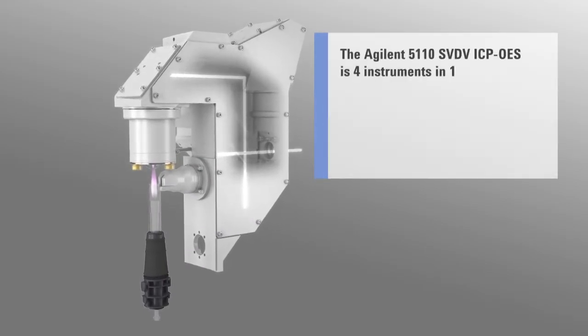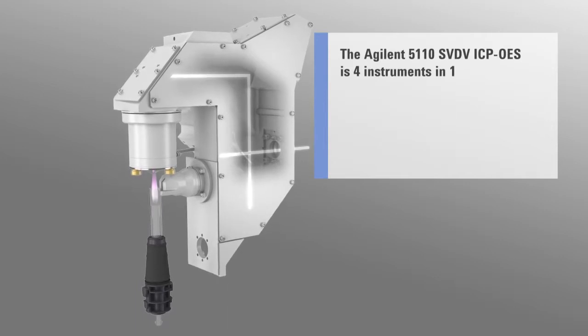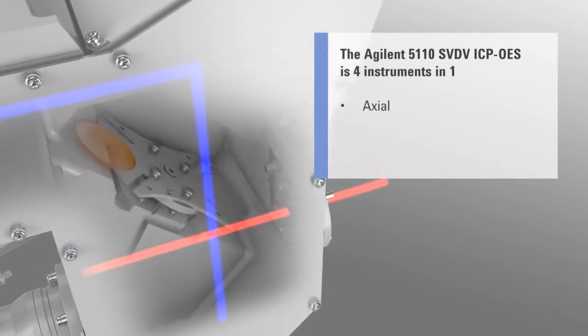In 2014, Agilent released the 5100 Synchronous Vertical Dual View ICP OES with dichroic spectral combiner technology. This set a new benchmark in speed of analysis, cost of ownership, performance and ease of use. The dichroic spectral combiner technology combines the light from the axial and radial views of the plasma into one synchronous measurement, allowing measurement of all elements and all wavelengths in a single measurement.